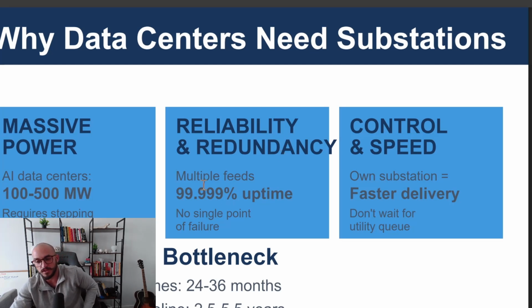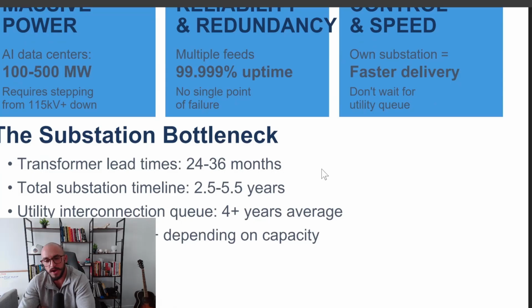The reliability and redundancy factor, where they need 99.999% uptime, is also interesting because the substation stepping down that power plays a role in that. If you own the substation you get faster delivery than if you're sharing one with somebody else. But a misconception is that substations actually hold power or have capacity - they don't. They're usually just stepping up or stepping down the power, not holding power generation or batteries saving it.